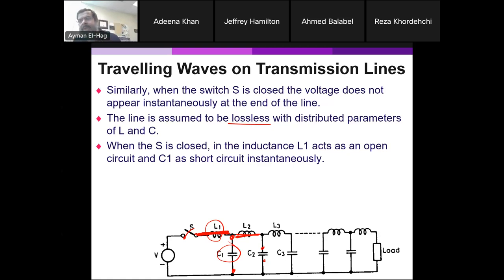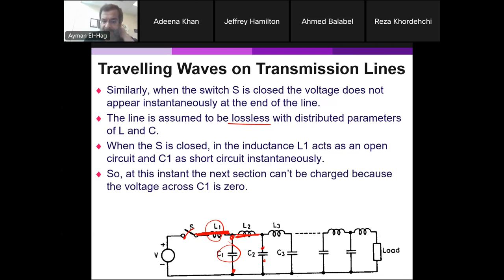And that will lead us to something very, very important. Now, when a surge happens at a certain point in the transmission line, it doesn't mean it will stay there. And if it doesn't impact the system at that point, it doesn't mean it will not impact the system a few kilometers from there. It might, as the wave propagates. So if there's a weak point, weak insulation, it might affect that insulation because the waves propagate with time.